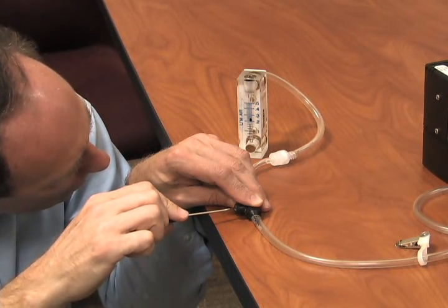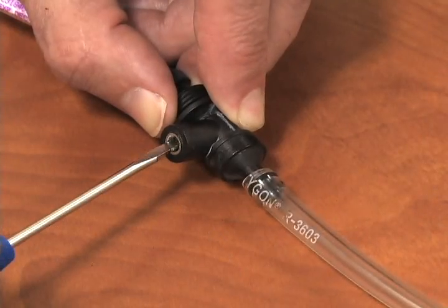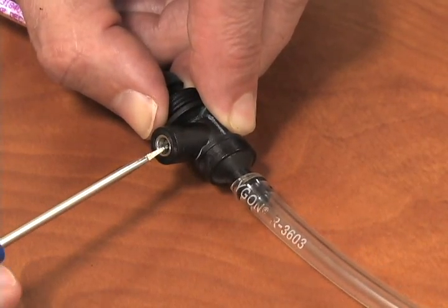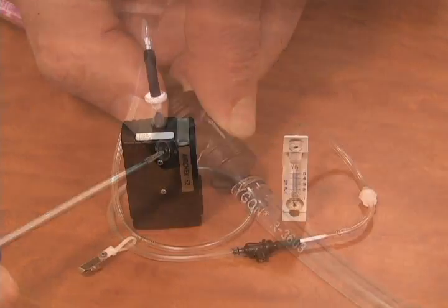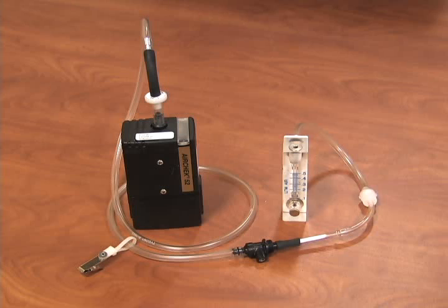Adjust the flow rate by turning the flow adjustment screw on the adjustable low flow holder until the rotometer indicates the desired flow. Be sure to take your rotometer reading at eye level and use the center of the float for the value. Do not adjust the flow on the pump at this point. Only adjust the flow on the low flow holder.